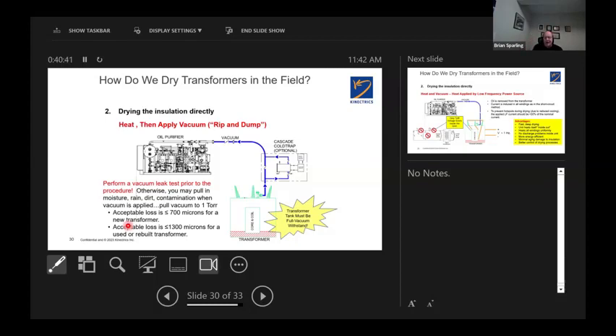And at some point you apply vacuum to the whole assembly with the oil out of the tank, or most of the oil out of the tank. Now that implies the tank must be fully vacuum resistant. You have to make certain of that before you start this. Now the thing is here, when you apply vacuum to anything, what happens? You lose all the heat. In a vacuum, there's nothing to hold the heat. So what happens inside is that things get cold quickly and things turn to frost. Once the vacuum is over, then you have to go back and heat it all up over again with hotter oil. This takes a long time.